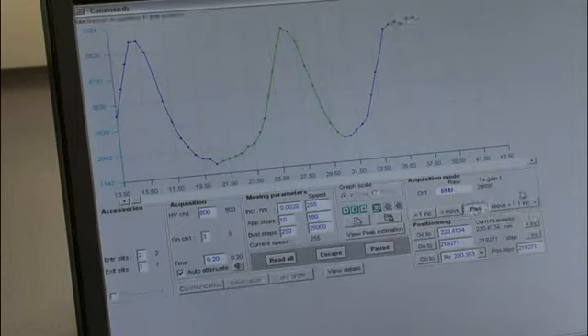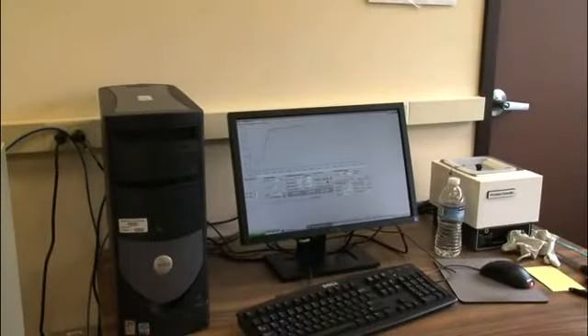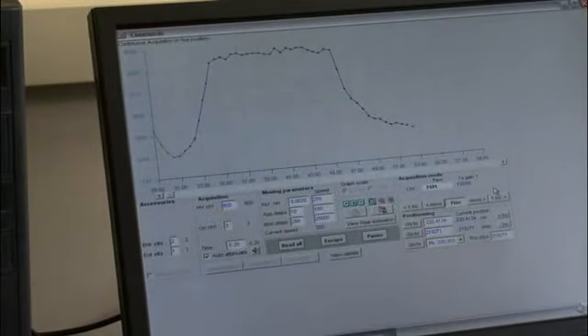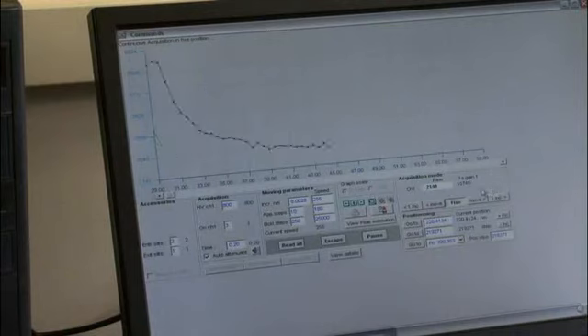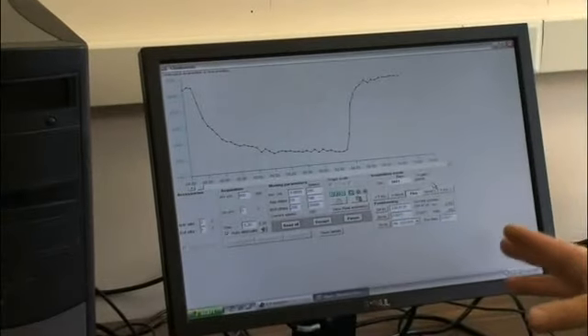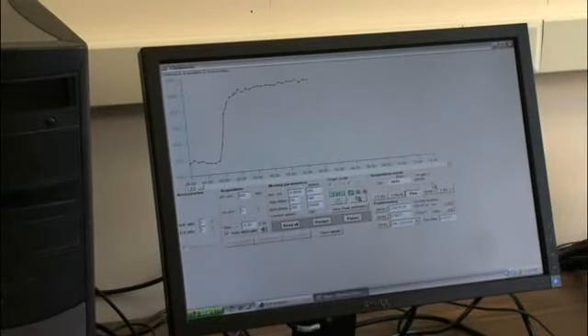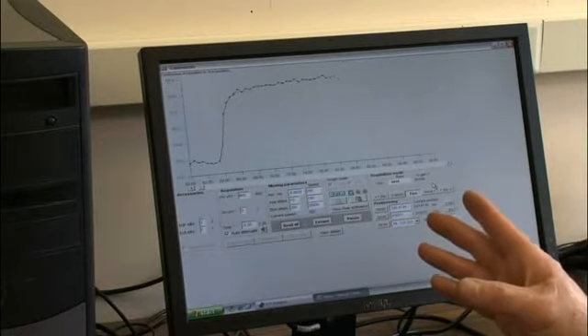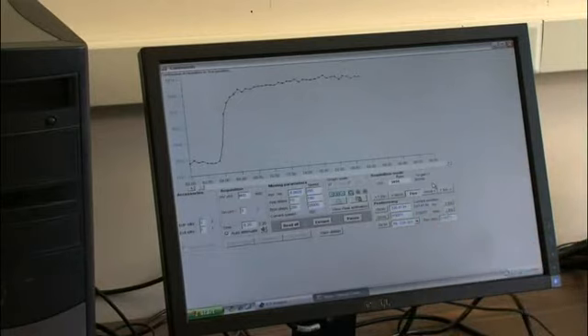Now I'm going to tell it to just look at it without moving. Could you hit the stop button on that pump? If I stop the sample from going in, it'll go away because there's no more lead going in there. Then if you hit stop again, it'll start. There are a lot of argon lines too. So if for some reason it finds this peak, but it doesn't go away when you stop the pump, then you know you're looking either at argon or carbon, or at nitrogen if you have nitrogen going in.